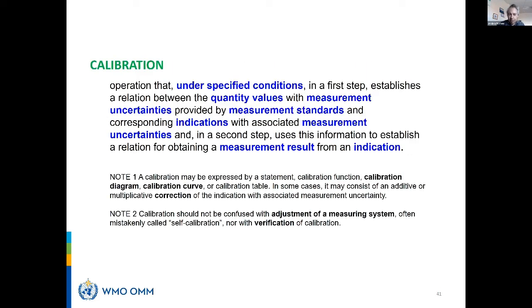The calibration is in fact an operation that is done under specific conditions, which are given by the calibration procedure. Your laboratory must be under temperature control conditions. Your operator must be skilled. Your instrument must be stabilized since a couple of days. Your current must be stable, and so on. Or if you are in the field, you have other conditions. It doesn't matter. It's horrible in the field, but if you recognize your condition, it's fine. But what does the calibration do?